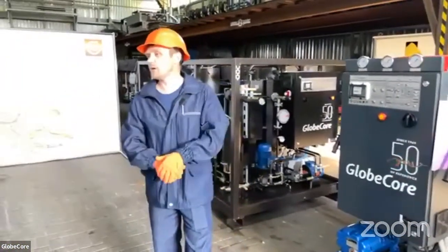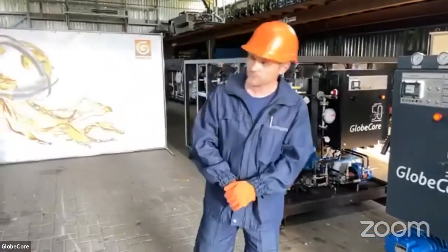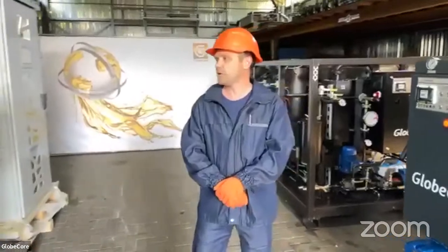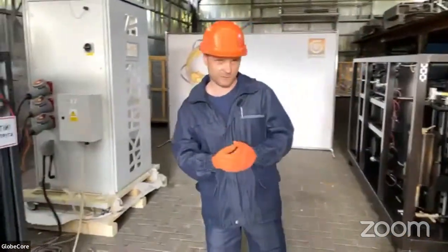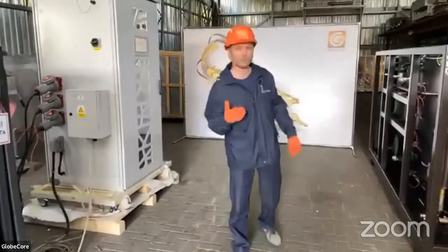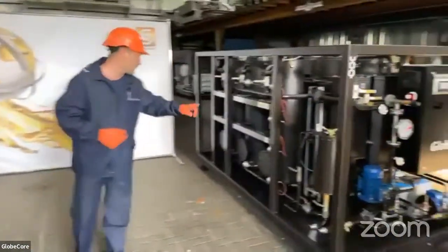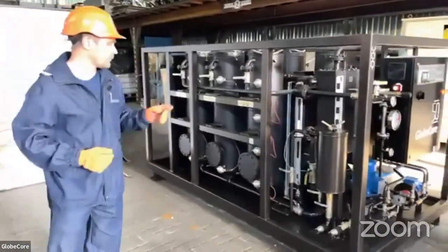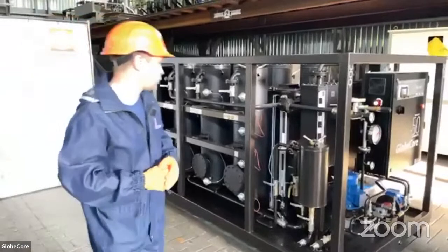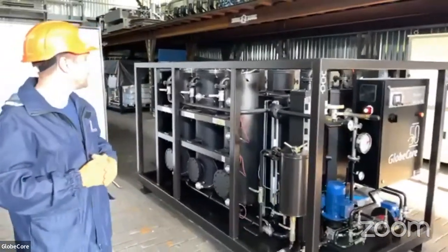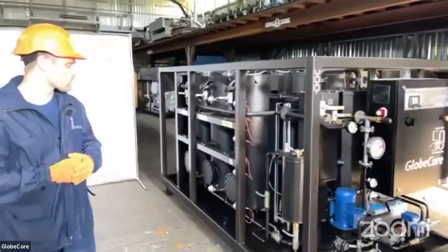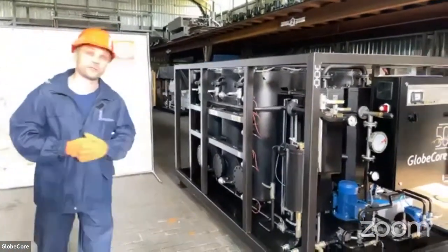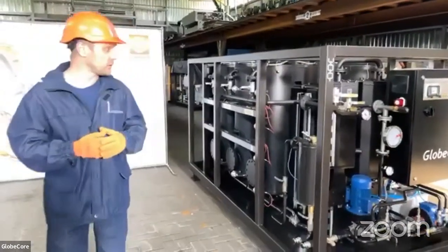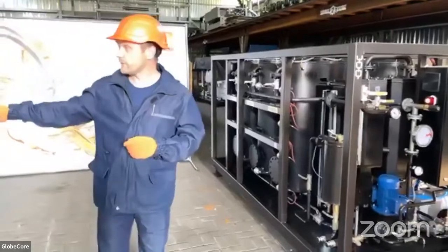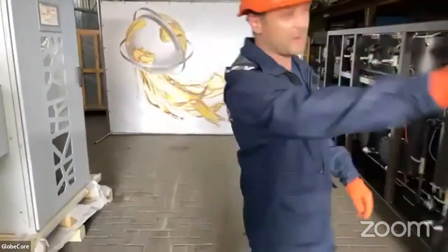And again, talking about the service of transformer, the highly demanded one is the regeneration technology. That's why the GlobeCore product line includes the whole range of regeneration units, particularly this one. Again, it is one of the simplest regeneration units. It has capacity of 200 liters per hour and can be successfully used in the complex with low frequency heating, drying unit. Even this one is enough. Drying unit and regeneration.